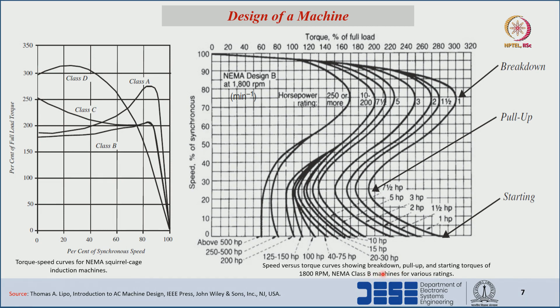For class B, the torque-versus-speed waveform shows breakdown torque, pull-up torque, and starting torque. Breakdown torque is the maximum torque; pull-up torque is where minimum torque occurs while speed is building up; and starting torque is what the machine is capable of generating at the time of starting. For a 5 HP machine, the breakdown torque is 230% of full load torque, pull-up torque is 120%, and starting torque is 180% of full load torque.